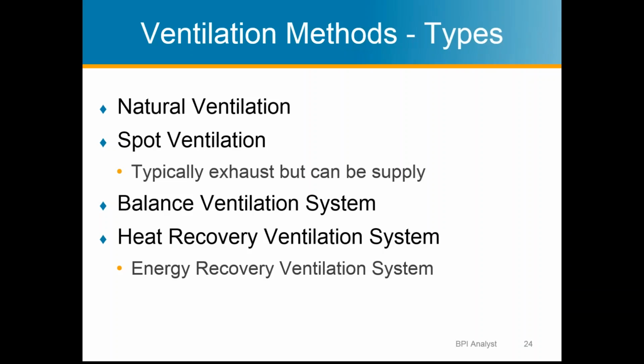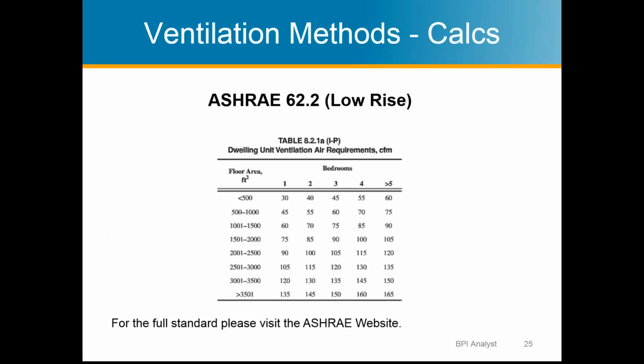So ventilation methods. There are 4 main methods for ventilation. The first is natural ventilation. That's like windows. We'll go into each of these in a little more detail. There's spot ventilation, which is typically exhaust only. That's what almost every house would have in their bathroom. Balanced ventilation systems, that's where there's both a supply and an exhaust into a house. And then a heat recovery ventilation system is really a form of a balanced ventilation system. We'll talk more about all of those.